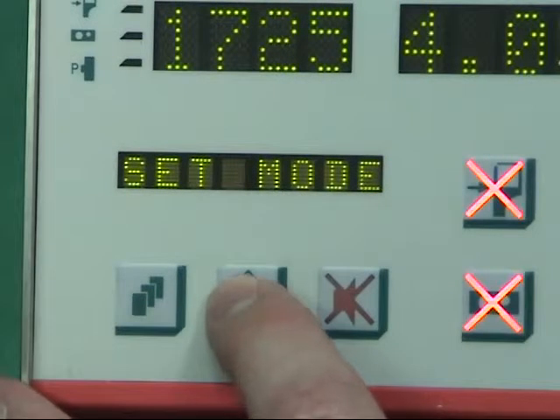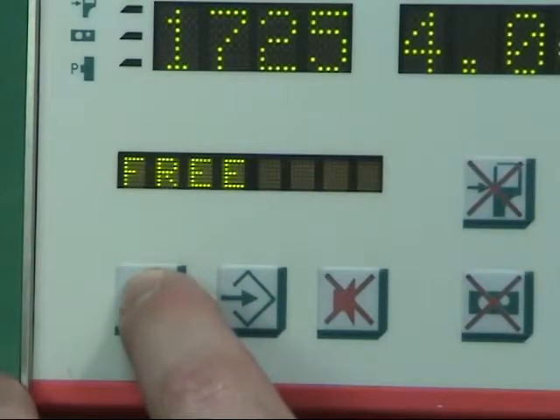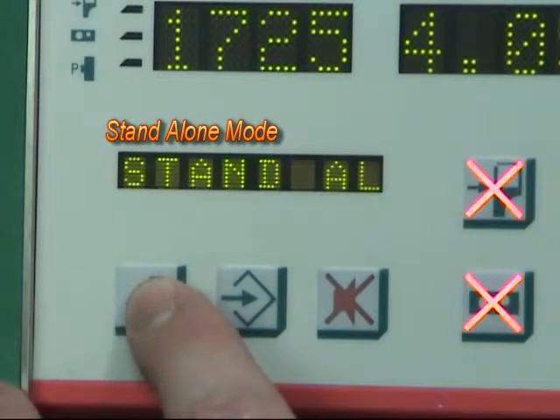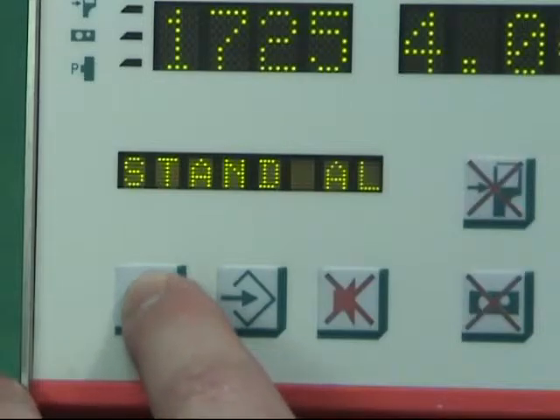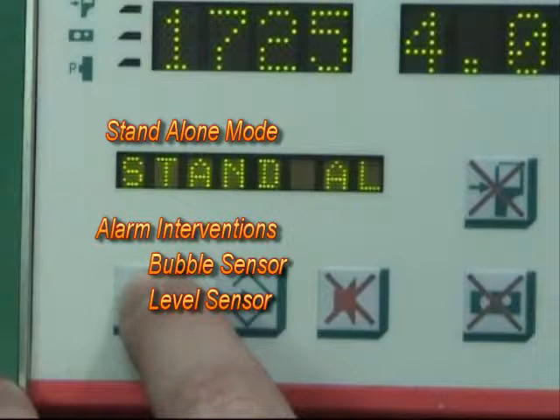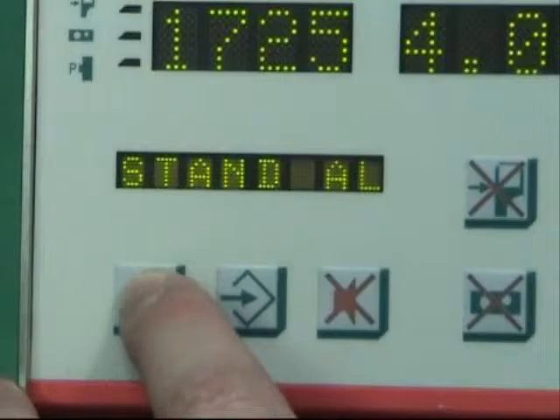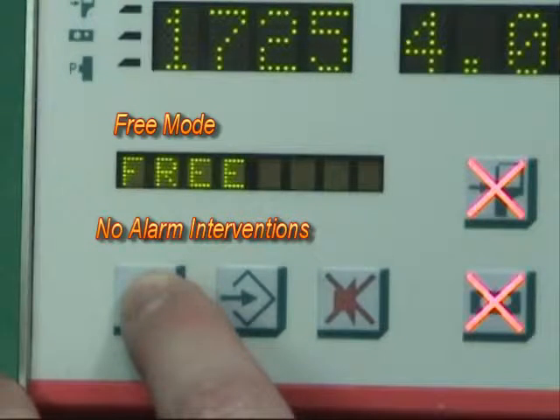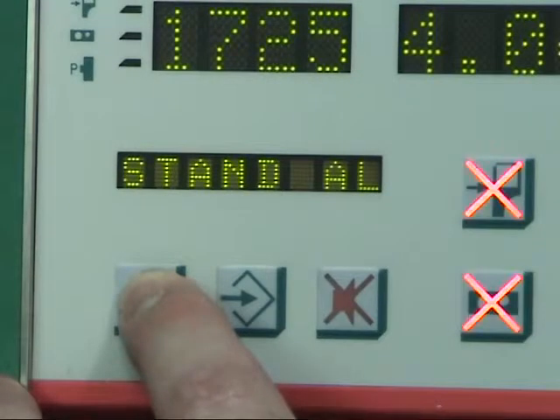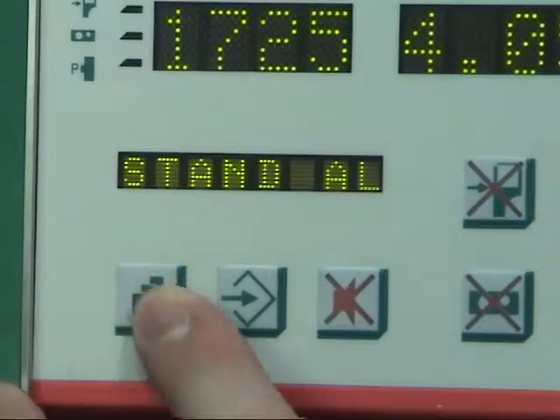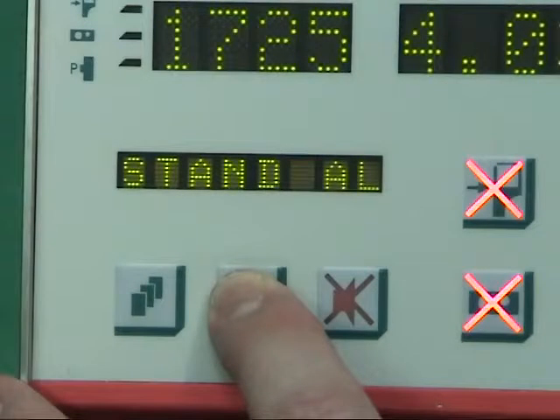2 of these modes are used primarily for ECMO. The standalone mode, or SA in the display, has alarm interventions through the internal bubble and level sensor connected directly to the Rotaflow console. This is the mode you want to be in while using this for an ECMO pump. The free mode, or FRE in the display, is a mode without any alarm interventions. This could be used if the alarms were not functioning correctly or were not enabled. To select the mode you want, simply hold down the Set button for 3 seconds.